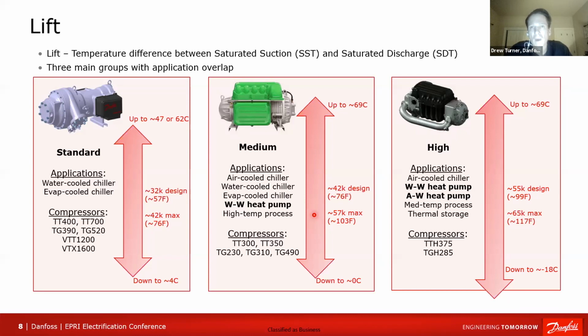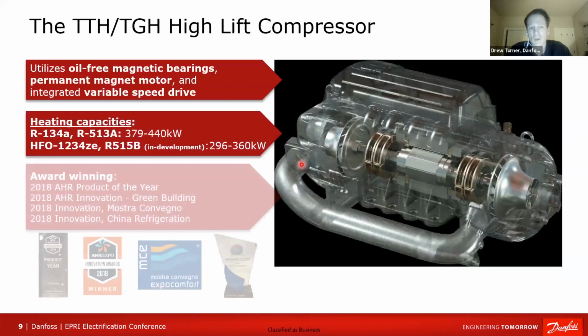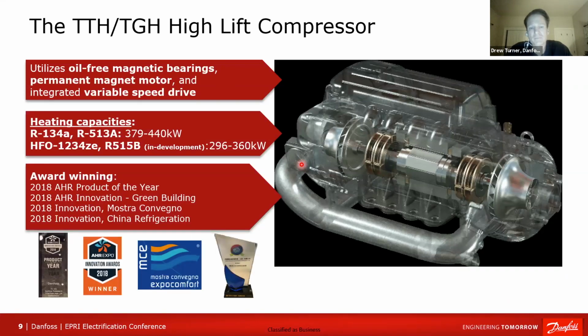We have compressors that are optimized for water-cooled chiller applications, more of a hybrid design for air-cooled chiller applications, as well as others. And then the most recent design, which I'm going to talk about in more detail next, is for water-to-water heat pumps. It's actually a combination, especially of these two, the medium and the high, that drives the most efficient solution for a specific application, especially a large water-to-water heat pump. And that's what I'm going to talk about a little more. But this is the compressor.